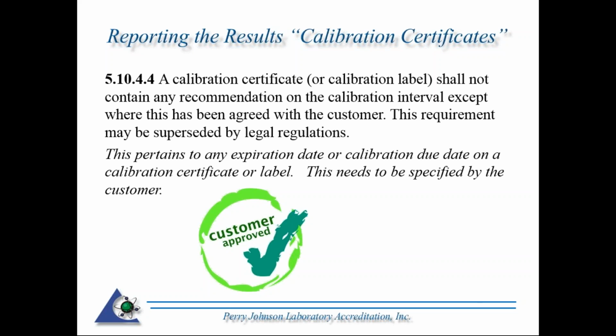So that cannot be expressed on the calibration report unless it's specified by the customer. Hence, you can't dictate that this calibration artifact has a calibration due date of 6 months. That has to be specified by the customer. It does not even need to be on the report, but if it is on the report, it needs to be specified by the customer.